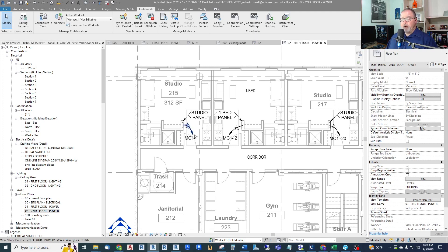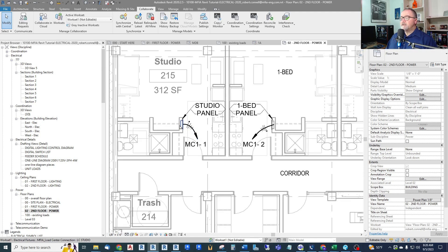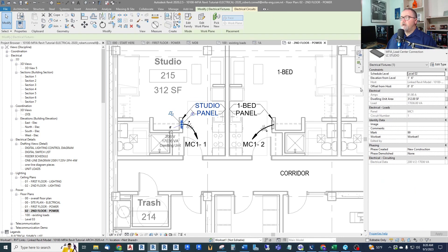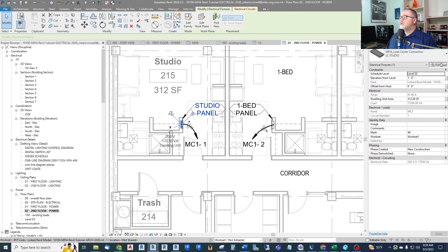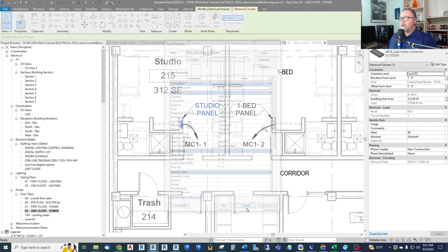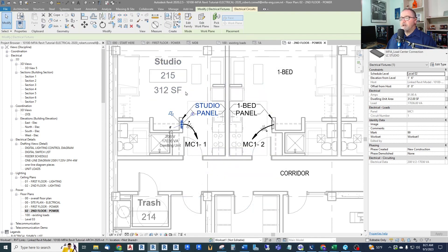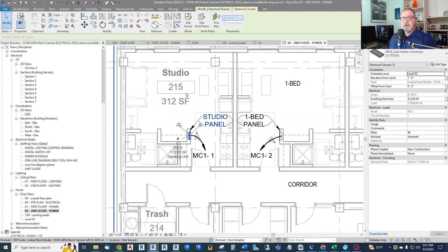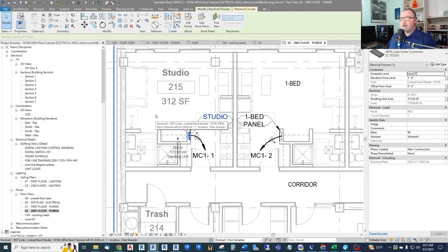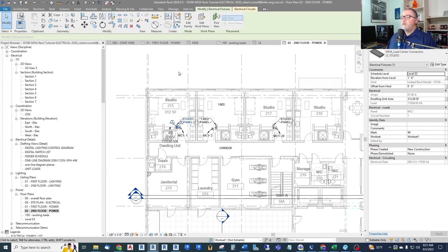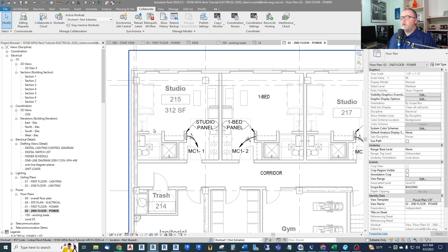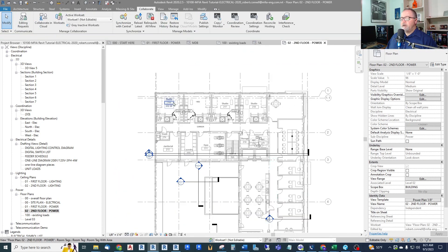Because as we learned earlier, this special load center equipment connection includes all of the connected loads that we need for our load summaries in our panels and our meter centers. So we don't need to show every one of these loads in here and we don't need to circuit every single one of these loads because they're circuited by square footage and residential means.